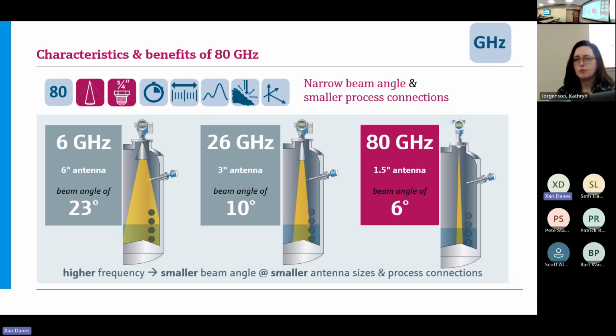Now the real appeal with higher frequency is that with a 1.5-inch antenna, I'm talking about a 6-degree beam angle. So with a higher frequency, I can have a smaller beam angle, even with a smaller antenna, a smaller process connection, whether it be a vessel flange or even a threaded port on a vessel.